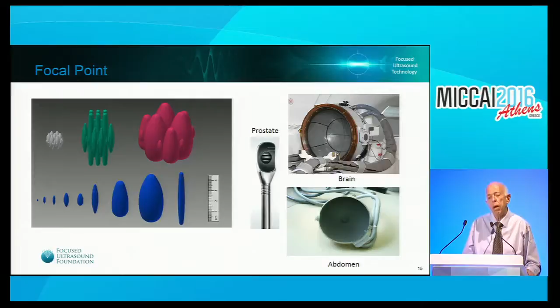So this is an illustration of different transducers. The middle one is a prostate transducer. The length of the active part is about 4 centimeters, and the width is about 2 centimeters. You already see the hint of image guidance, because the ball in the middle is the ultrasound imaging transducer. On the upper right, you see a brain transducer. This is the one coming from Insightec. And below, the same one you saw in the earlier clip, for abdominal targets. Based on the amount of energy and the type of transducer, its size, the F number mainly, and its geometry, we can control the size and orientation of the focus.